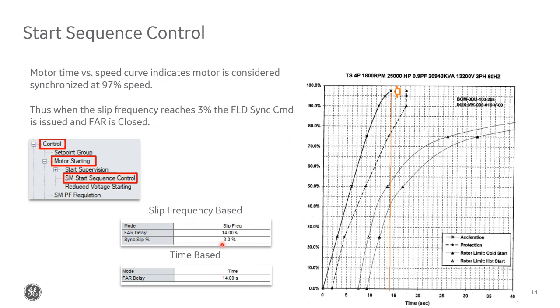So when the relay measures that the slip has reduced to 3%, it'll trigger a closure of the field application contacts to bring in the DC supply. The other option is to control based on time. In this case, we need to set the field application relay delay to the time indicated at the endpoint of the acceleration curve when it indicates it's up to speed. So in this case, that's about 14 seconds. So 14 seconds after we register a motor starting state, the 869 will assume the motor's up to speed and then it'll close the field contacts.